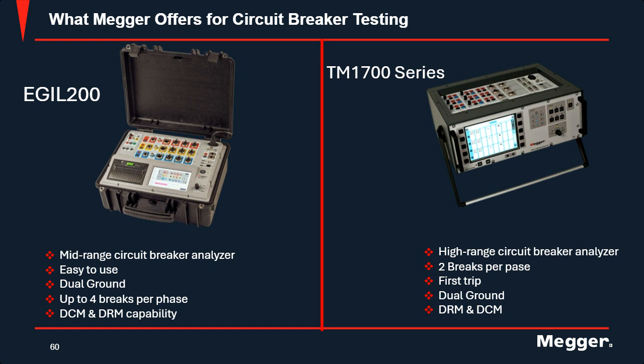On your higher range circuit breaker analyzers, you got your TM1700 series. It's a higher range circuit breaker analyzer, like I said. This is good for 2 breaks per phase. It does allow you to do first trip, dual grounding, dynamic resistance measurements, and dynamic capacitance measurements.